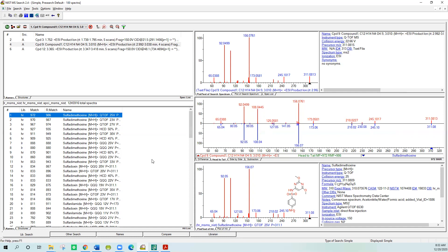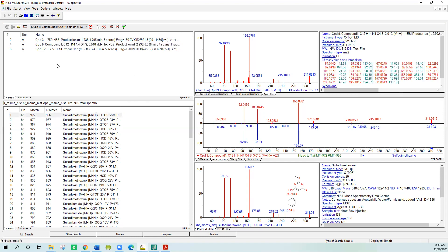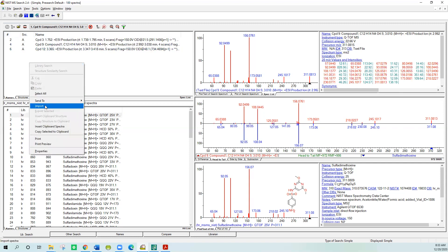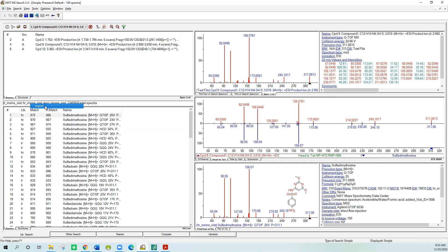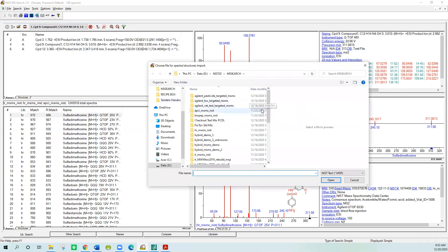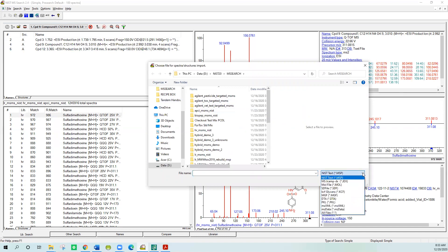But that's pretty much how you do the back and forth between them. It's very easy. Personally, I've used Agilent, I've used Thermo, and I've used Waters, and all those have the buttons internally that easily transfer things back and forth. Some of the manufacturers might not have the button, but they might have another way. Another way is if you right-click on our search import box here and say import. And on the import list you can see, if you go down to the bottom here, there's lots of different ways you can import files. And one way the manufacturer might do is to export their spectrum of interest into one of these file formats, and then you would have to import it into the program to process.